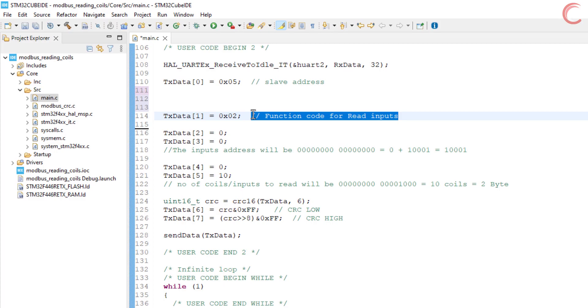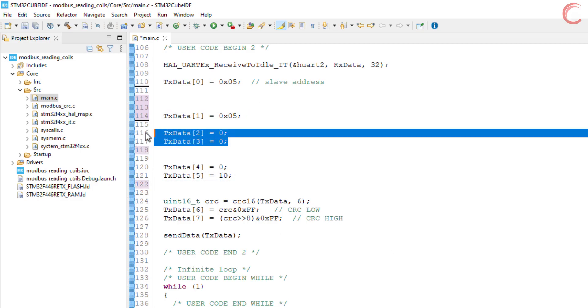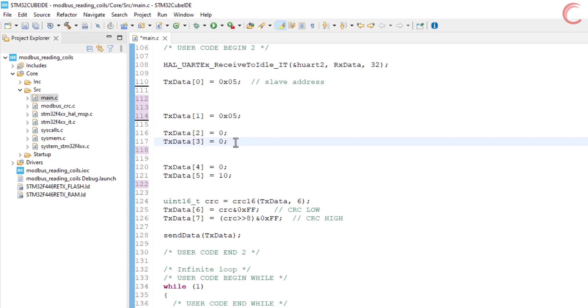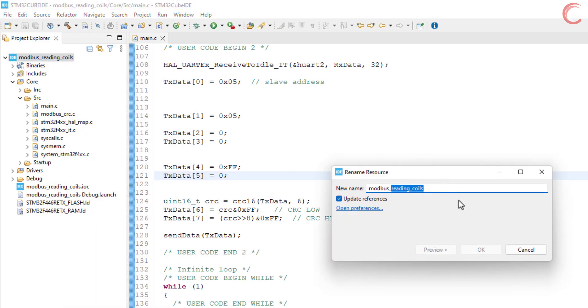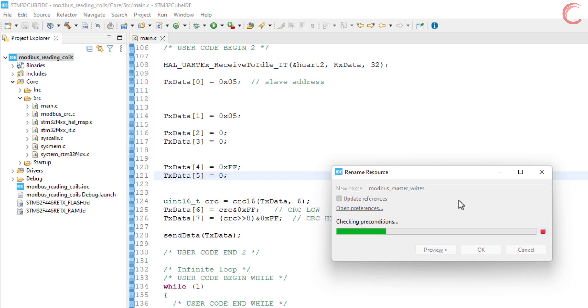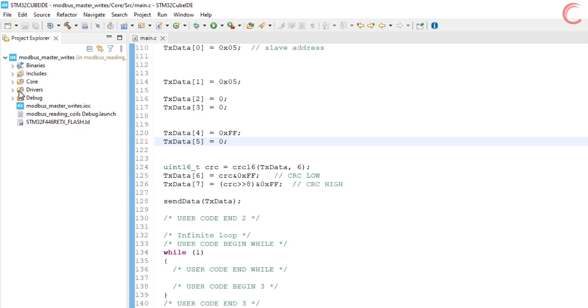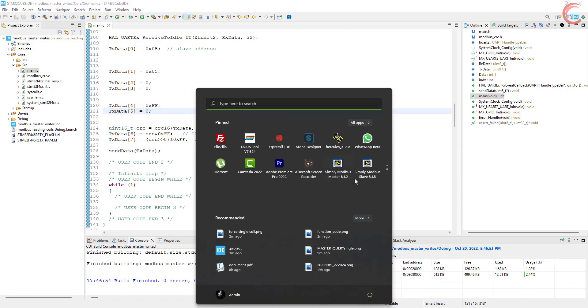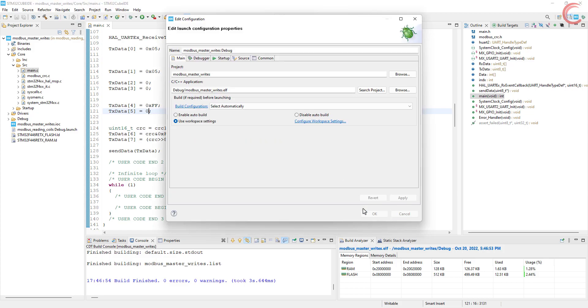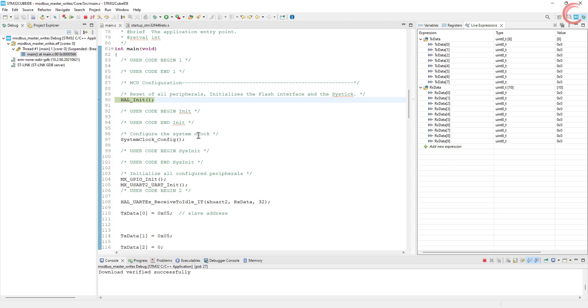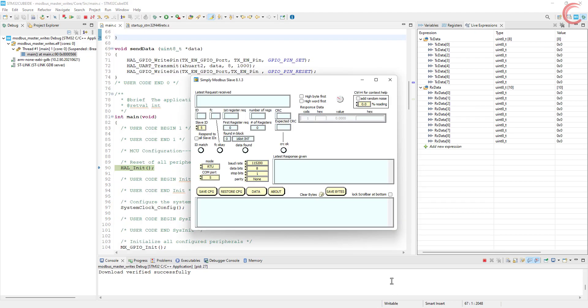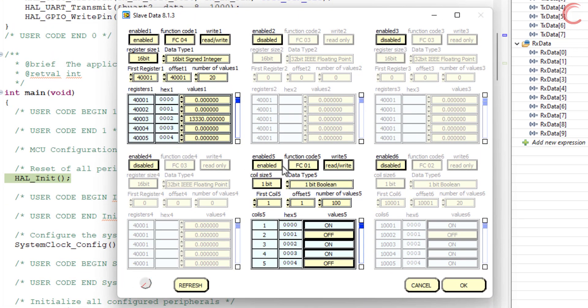Let's try this. We have function code 5 to write a single coil. I am keeping the coil address as 0, which means the actual coil address will be 1. I want to set the coil at this location, so the data is going to be 0xFF followed by 0x00. The CRC will be calculated as usual, giving us a total of 8 bytes of TX data. Let's build and run this project. I am renaming the project to Modbus Master Writes. Now let's debug it and put a breakpoint in the callback function. The slave will send the response, so we will know when it does.